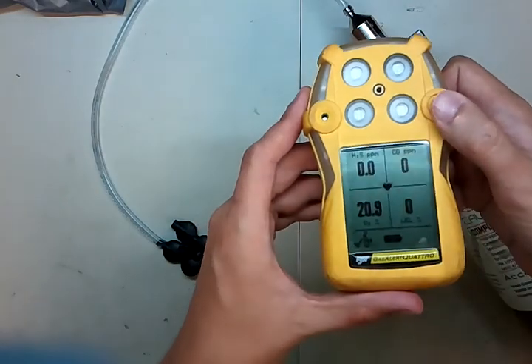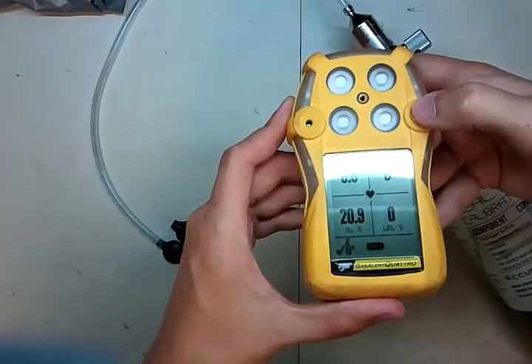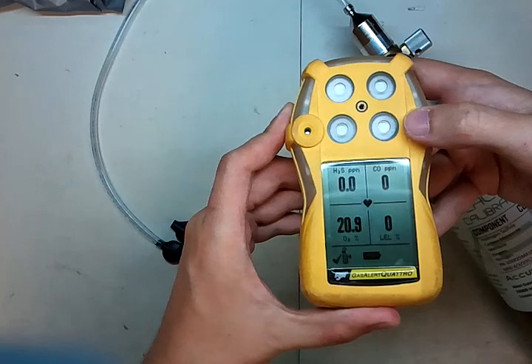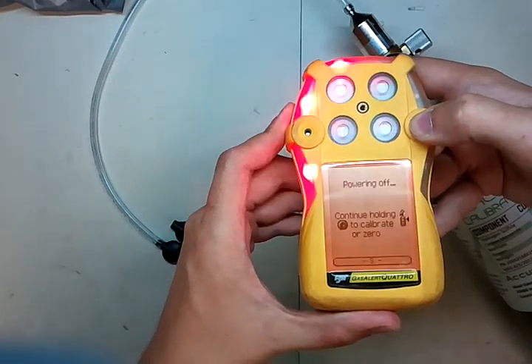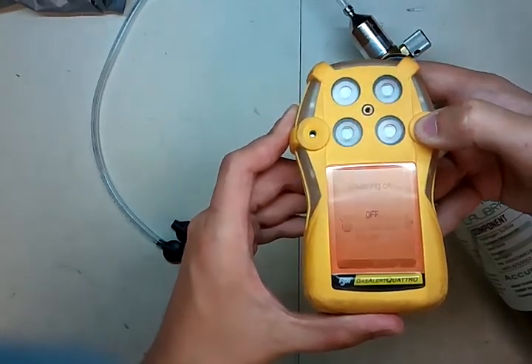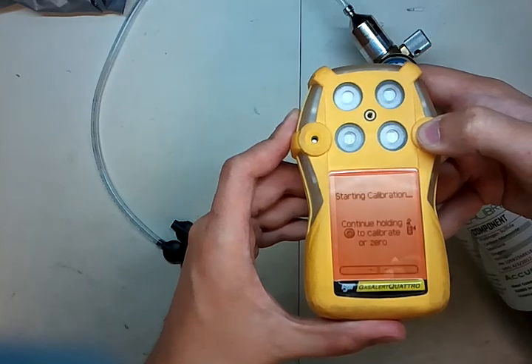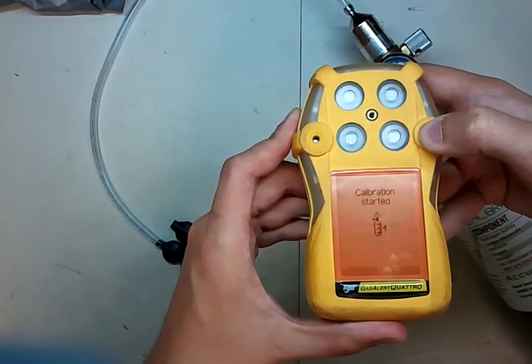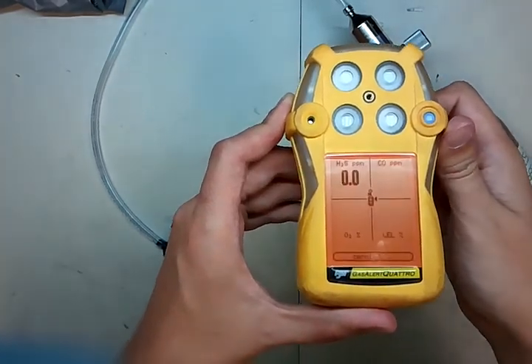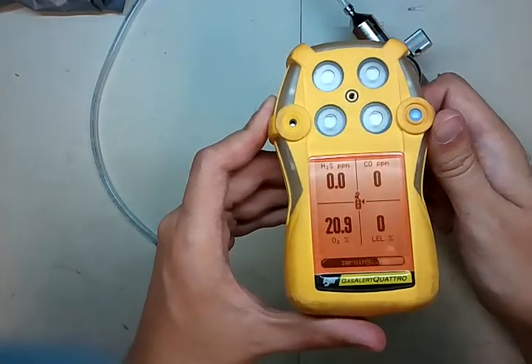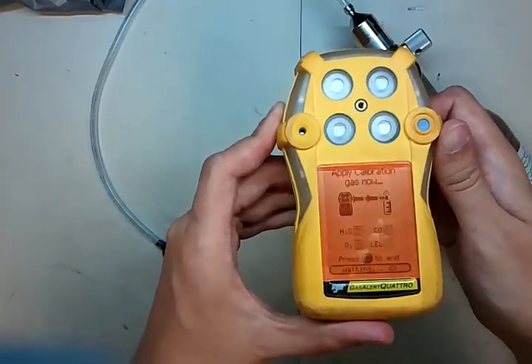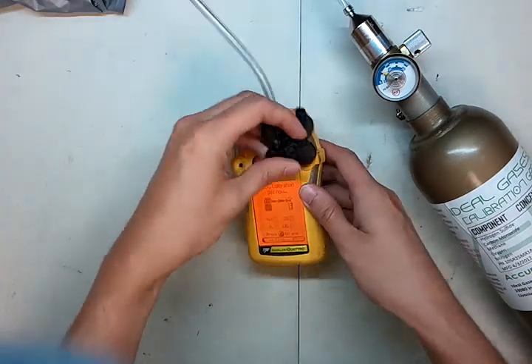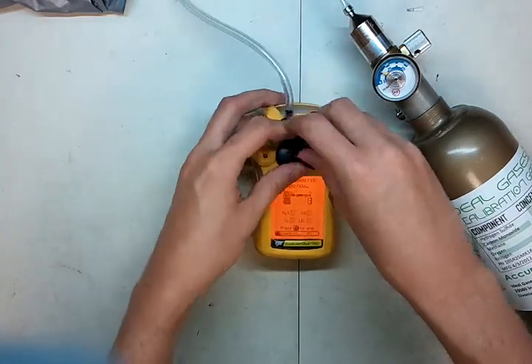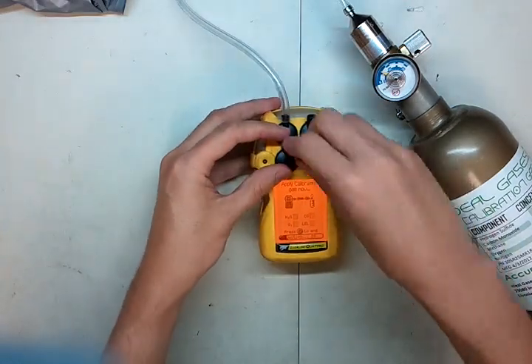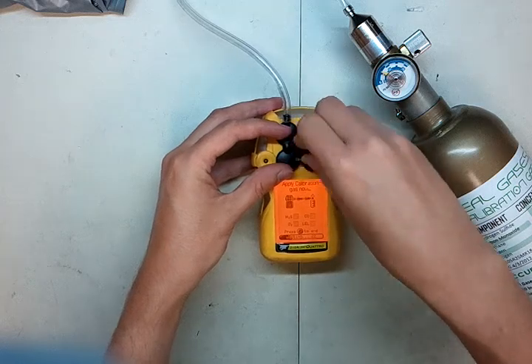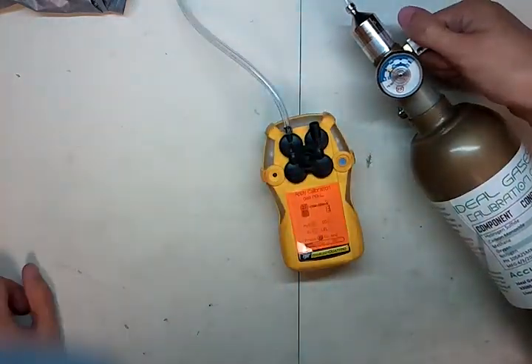And this one's really easy to do. All you do is take this button here, press and hold it. It's right here. And you're going to continue holding it, and the menu even says just keep holding it once it's off, and it'll go into cal mode. Sounds kind of like a video game. So now it's going into zero mode. Does that real quick, and it says apply the gas now. So all we do, put this on the middle, start screwing it in. Now turn your gas on.